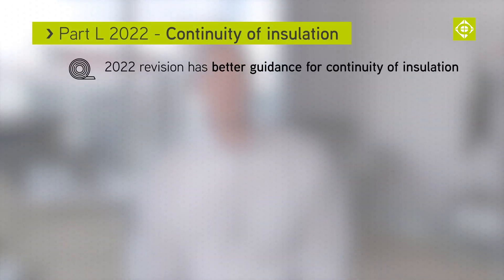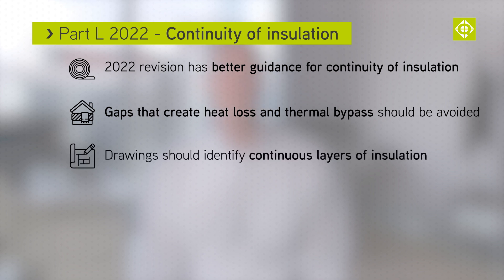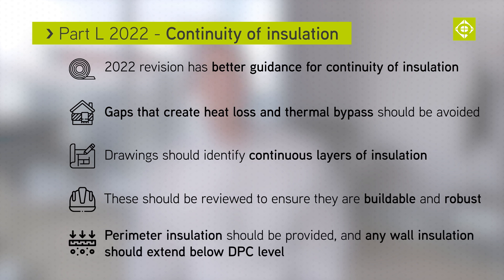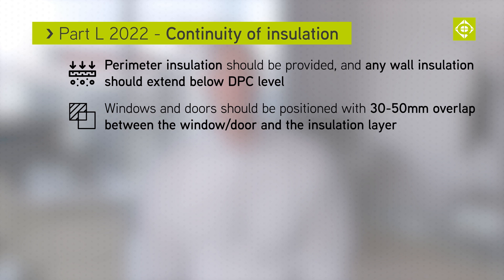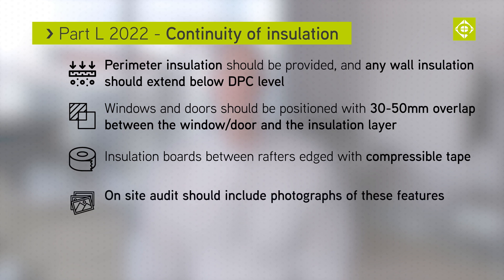The 2022 revision introduces better guidance for continuity of insulation. Gaps that create heat loss and thermal bypass should be avoided. Drawings should identify continuous layers of insulation and be reviewed to ensure they are buildable and robust. Perimeter insulation should be provided and wall insulation should extend below damp proof course level. Windows and doors should be positioned with a 30 to 50 mm overlap between the window or door and the insulation layer, and insulation boards between rafters should be edged with a compressible tape. The on-site audit should also include photographs of these features.